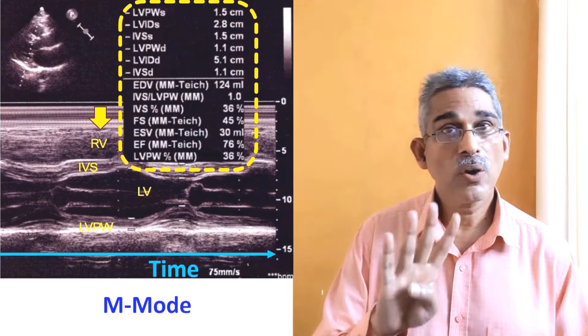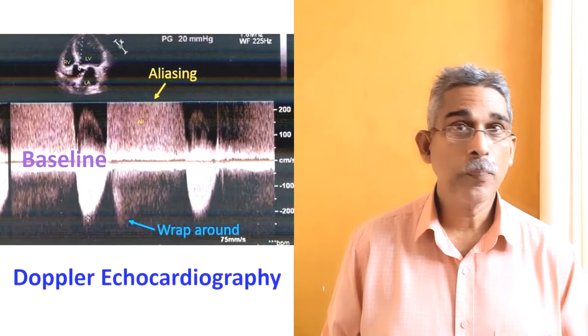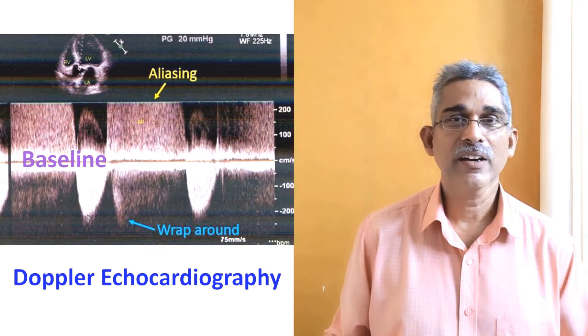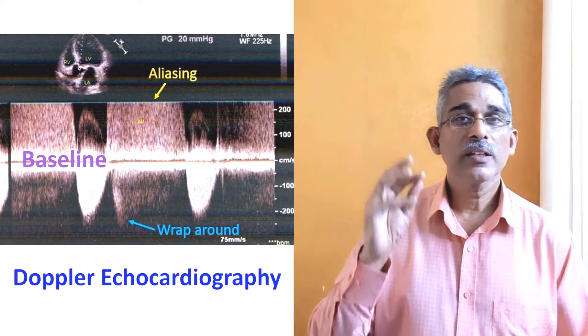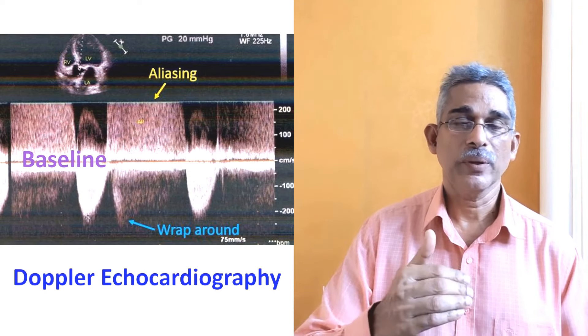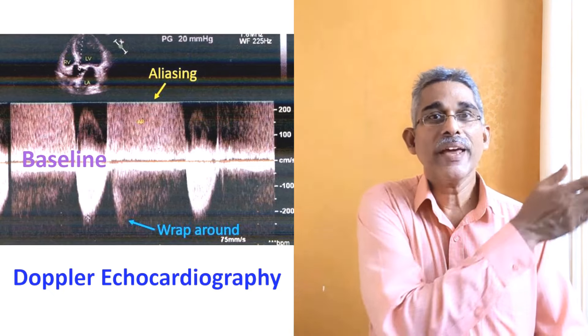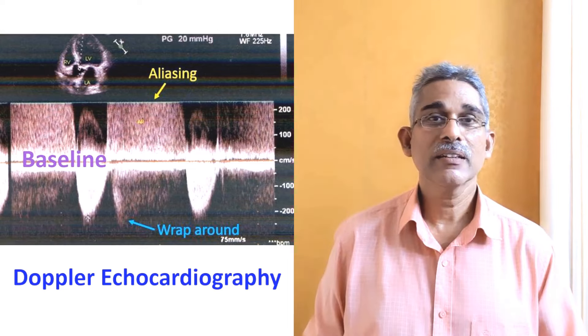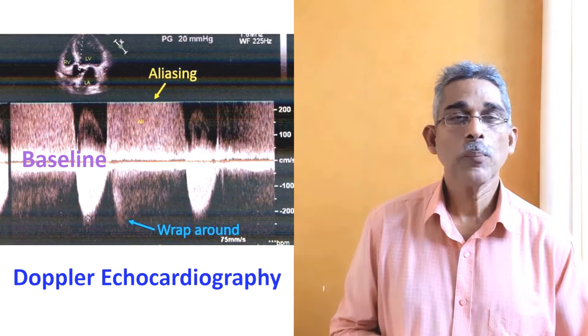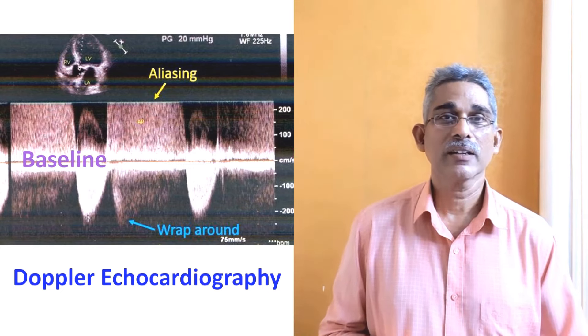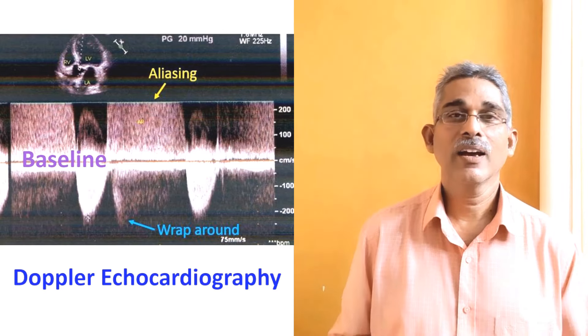Live 3D is known as 4D echocardiography. There is another mode known as Doppler echocardiography, which measures the Doppler shift. You may have noticed that when sitting in a railway station, as a train approaches you the whistling sound has a different frequency, and when it moves away the frequency changes. This is known as the Doppler shift. When this change in frequency is detected, you can find out the velocity of the object. Similarly, an ultrasound beam is focused on red blood cells in the heart and blood vessels.